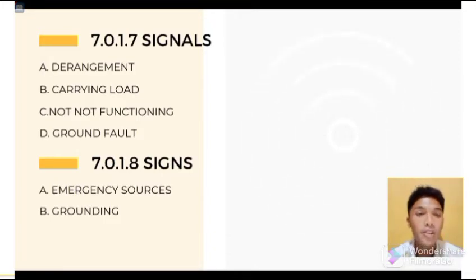7.0.1.8 Emergency sources. A sign shall be placed at the service entrance equipment indicating type and location of on-site emergency power sources. Letter B, grounding. Where the grounded circuit conductor connected to the emergency source is connected to a grounding electrode conductor at a location remote from the emergency source, there shall be a sign at the grounding location that shall identify all emergency and normal sources connected at the location. So, it is under the sign and it is for the grounding.